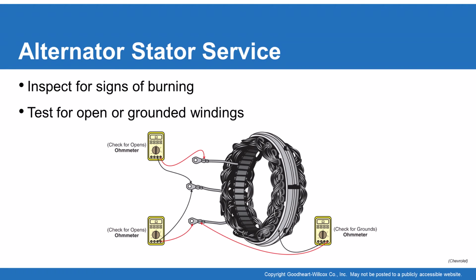So we'll set our meter to ohms, and then we'll check between the pairs, and then we'll also check between the actual windings themselves to see if we have any opens or anything that's grounded together. Sometimes the insulation around those windings will actually wear off, and then that shorts the wires together.